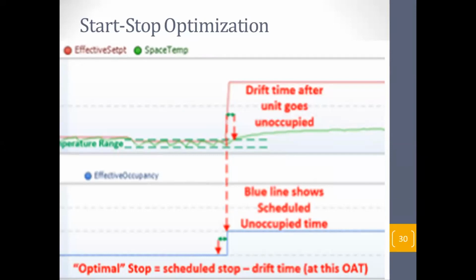Very simple. You stop your chillers, condenser water pumps and cooling towers, and circulate chill water. To make things simple, assume that they don't have any package units, only a central plant. So your chill water pumps are running and the air handling units are running. See how long it will take for the space temperature to go beyond your threshold. If you are supposed to give maximum 25 degrees, see how long it will take to go beyond 25 degrees. Let's say it's half an hour. Then, if you're supposed to give air conditioning till 6 o'clock, you can stop your chillers at 5:30. Without spending anything, you can save millions. Right? That is one aspect.